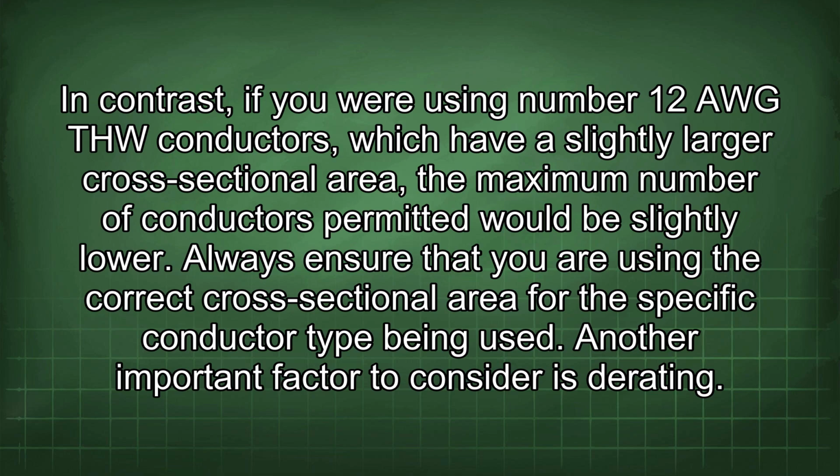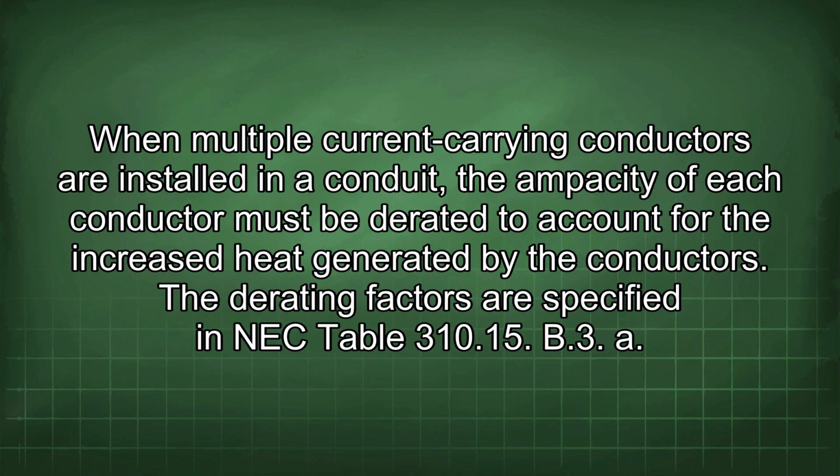Another important factor to consider is derating. When multiple current-carrying conductors are installed in a conduit, the ampacity of each conductor must be derated to account for the increased heat generated by the conductors. The derating factors are specified in NEC Table 310.15(B)(3).